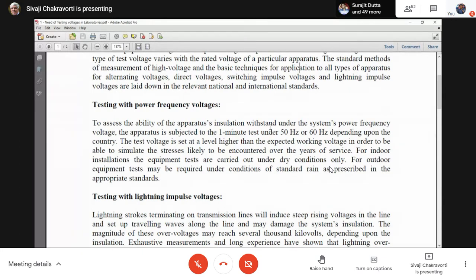When we do the high voltage testing, we don't do it at its normal operating voltage, say 11 kV. But when it is online, connected to the high voltage line, there will be a lot of overvoltages. These overvoltages are of different types. The most common overvoltages will be the power frequency overvoltages.